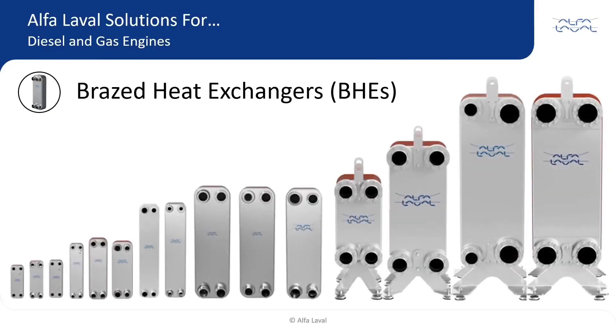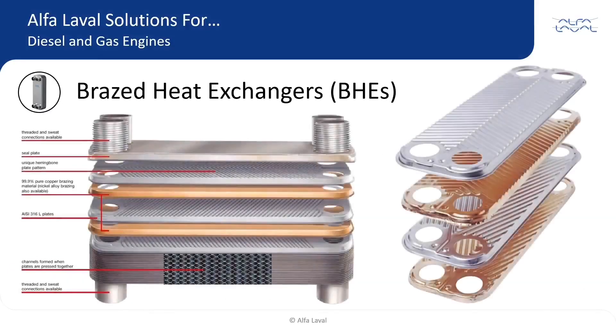Alfa Laval is the world leader in brazed plate heat exchangers, has produced them since the 1970s, and continually develops this technology. Alfa Laval offers a wide range of BHEs that can be as much as 80% smaller and more efficient than shell and tube heat exchangers. Each BHE is manufactured with very thin corrugated stainless steel plates brazed together with a sheet of 99.9% pure copper. The plate pack and copper are then compressed and put into a vacuum furnace where the plates bond together, yielding a compact yet highly efficient heat exchanger.